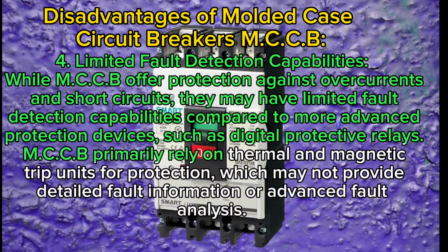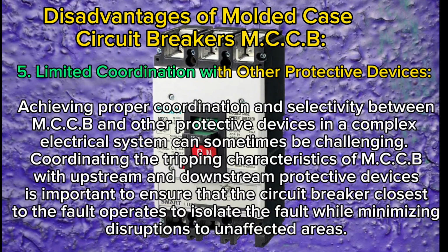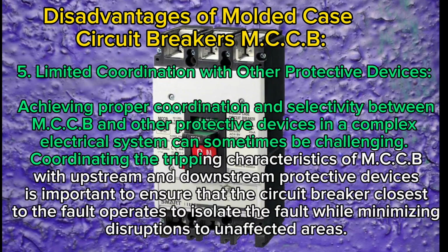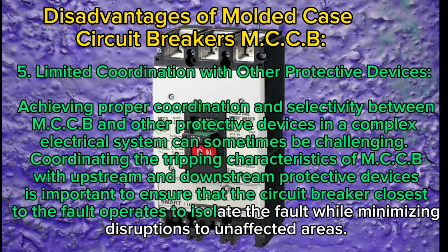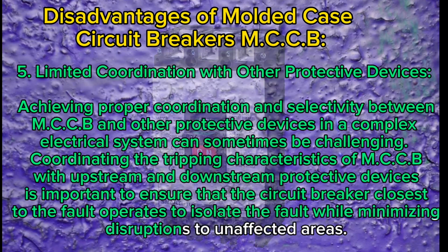MCCBs primarily rely on thermal and magnetic trip units for protection, which may not provide detailed fault information or advanced fault analysis. 5. Limited coordination with other protective devices. Achieving proper coordination and selectivity between MCCBs and other protective devices in a complex electrical system can sometimes be challenging. Coordinating the tripping characteristics of MCCBs with upstream and downstream protective devices is important to ensure that the circuit breaker closest to the fault operates to isolate the fault while minimizing disruptions to unaffected areas.